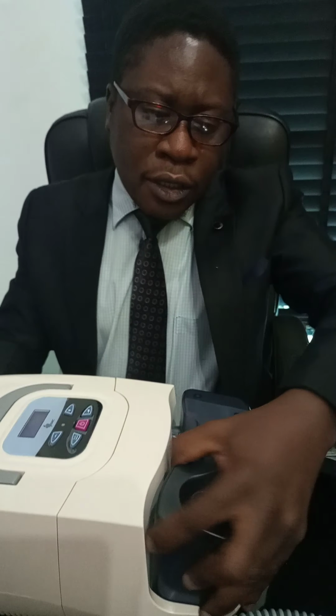The basic part that needs to be maintained is the humidification chamber. This needs to be filled with distilled water up to the point marked here. Use distilled water rather than tap water, because tap water forms mineral deposits at the floor of the humidification chamber, and that damages the chamber, which may need to be replaced if spoiled. So use distilled water, which you can get in any store where such water is sold, rather than tap water because of the minerals. Before use, fill your humidification chamber with distilled water up to the marked point, and then slot it in like this.